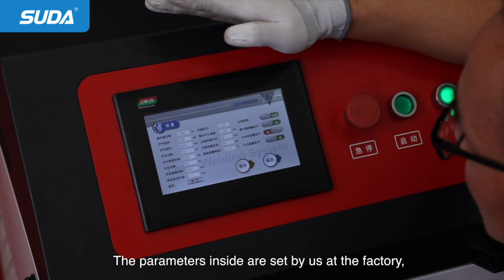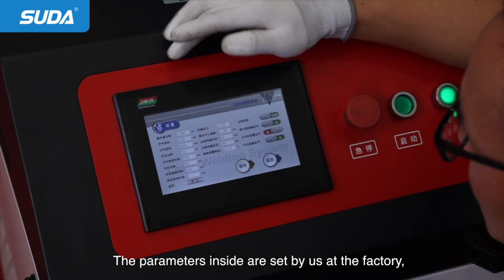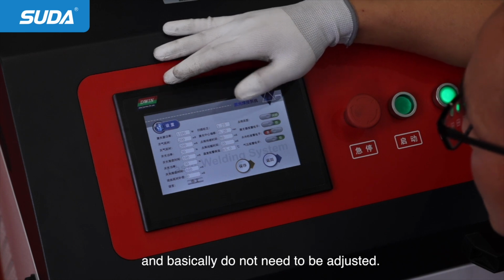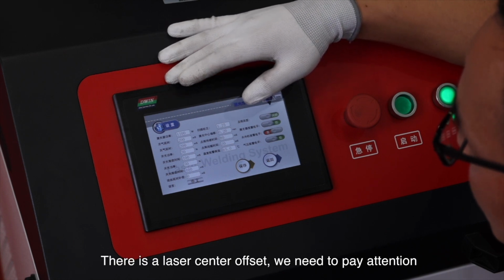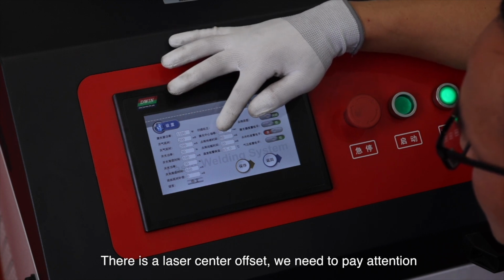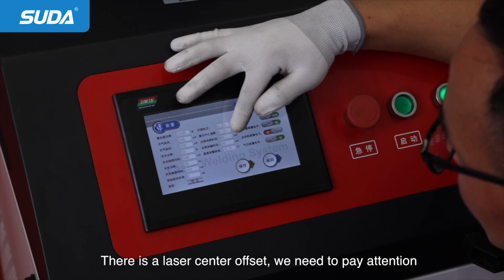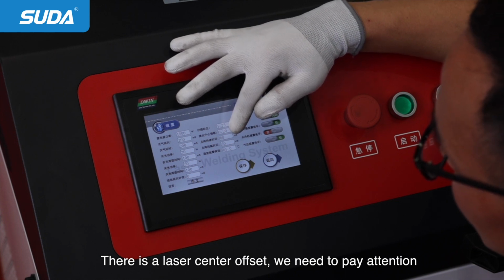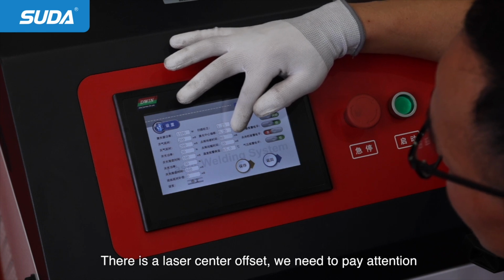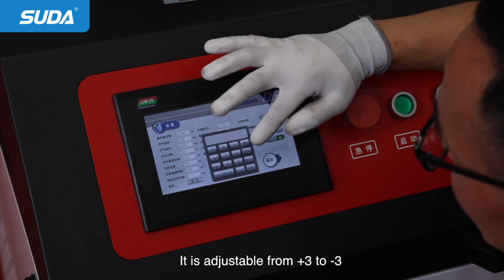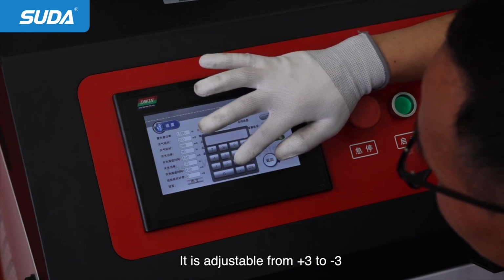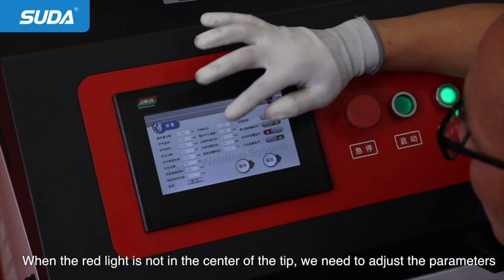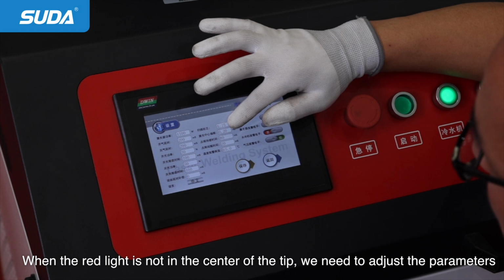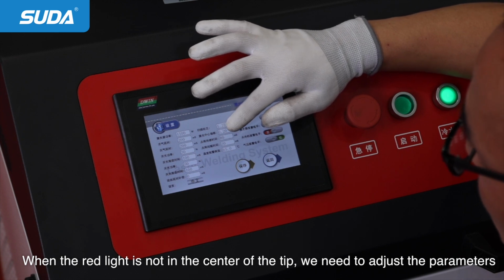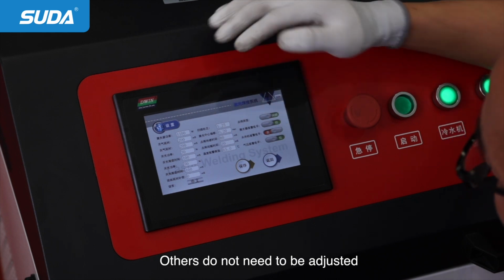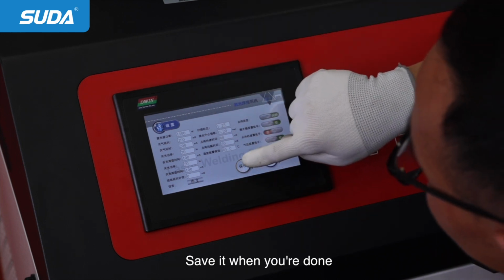The parameters inside are set by us at our factory. Basically, you don't need to adjust those parameters. And there is a laser center offset, which we need to pay attention to. It is adjustable from +3 to -3. When the red light is not in the center of the tip, we need to adjust the parameters. Others do not need to be adjusted. Save it when you are done.